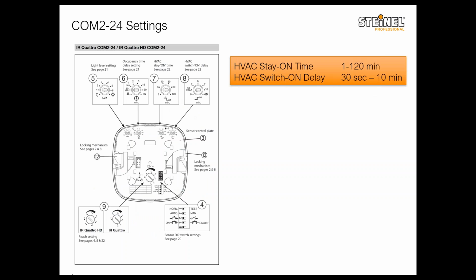Just a refresher, most of you probably know that we have our line of Control Pro sensors in several models: PIR, dual tech, and ultrasonic only. Throughout the whole range, regardless of the technology, we have the COM2-24 sensors. A COM1-24 sensor, which is the most commonly used one, will just have a lighting output to control the lighting. So, a basic timer for the lighting and lux level sensing for some daylight responsive control.